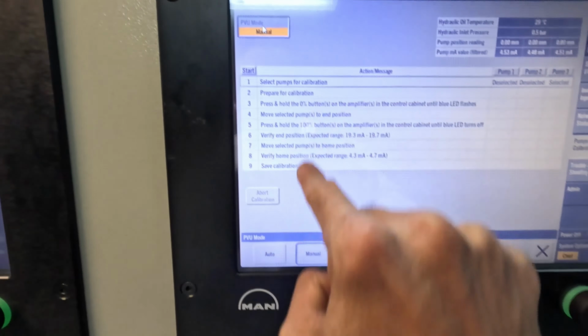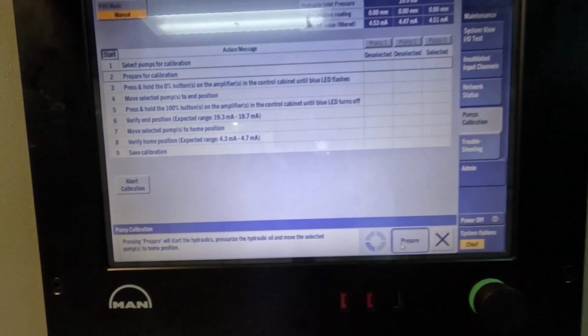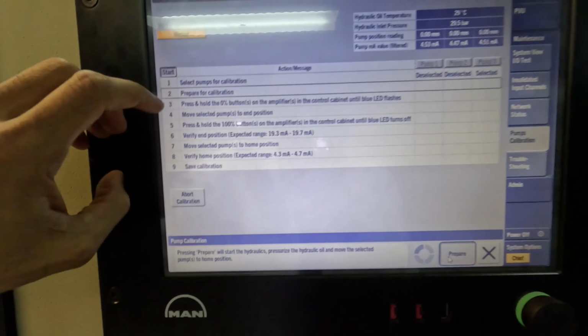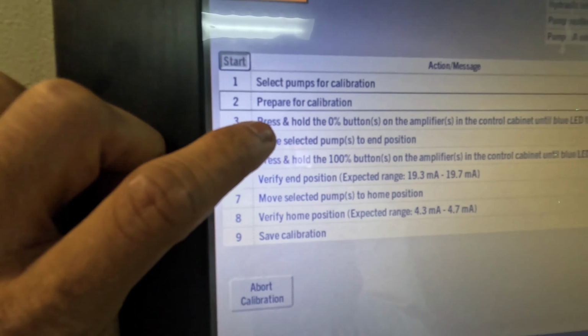Now I press start. Okay, Rohit, I'm pressing the start button now. So press proceed, and now it's preparing the pumps for calibration. You see the hydraulic pressure starts building up. Rohit, we are on step 3. This step is preparing for calibration, and it will bring up the pressure. Once the pressure is up, it will ask me to press and hold the 0% button. Remember the blue LED, the 0% button on the amplifier. That's the button the cargo engineer will press in the cargo switchboard room.